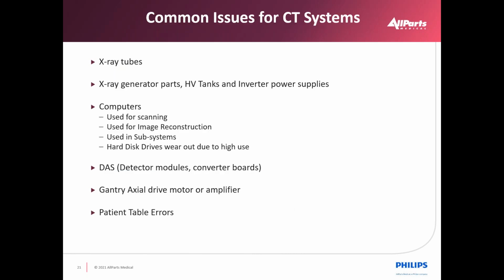So common issues we've identified as X-ray tubes, just because of the expense, but also high voltage, time, and we talked about the rotating anodes, so the bearings in that tube will wear out due to just aging out and being conventional ball bearings as well. The other risk items have to deal with high voltage as well, and that is the high voltage tanks themselves can produce arcing, and the inverters that drive them at these power levels can also fail. So we see a lot of challenges with regards to these parts degrading over time as well. Then on the opposite end, where we do the control, reprocessing data, we have the computers.